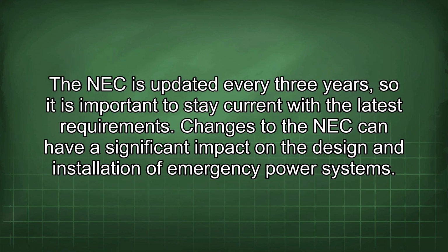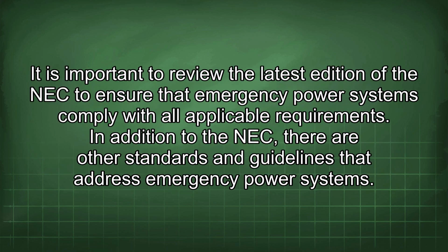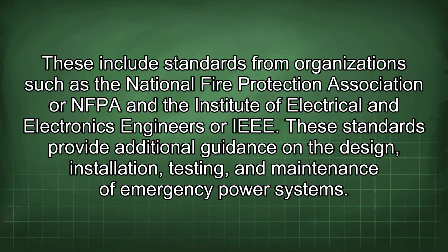The NEC is updated every 3 years, so it is important to stay current with the latest requirements. Changes to the NEC can have a significant impact on the design and installation of emergency power systems. It is important to review the latest edition of the NEC to ensure that emergency power systems comply with all applicable requirements. In addition to the NEC, there are other standards and guidelines that address emergency power systems. These include standards from organizations such as the National Fire Protection Association, or NFPA, and the Institute of Electrical and Electronics Engineers, or IEEE.